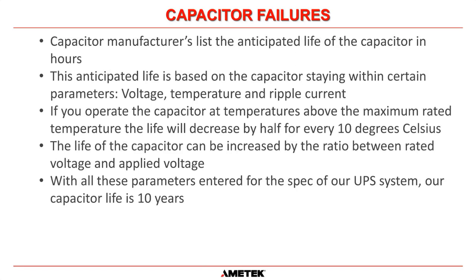If you operate the capacitor at temperatures above the maximum rated temperature, the life of that capacitor will decrease by half for every 10 degrees Celsius above its operating temperature. That's significant. Now, obviously, that increase in temperature by 10 degrees has to be all the time. So basically, if you run a capacitor at 10 degrees Celsius above what it's supposed to be for a year, what they're saying is you have now reduced the life of that capacitor by half. So if it's a 10-year capacitor and you run it at 10 degrees above the manufacturer's tolerance for 5 years, then 5 years will be the end of life for that capacitor.